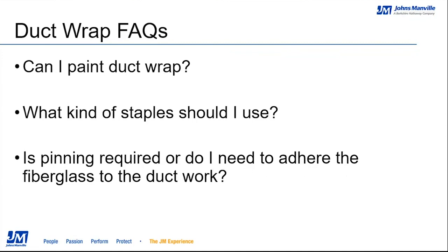using, and therefore we can basically say it's going to void our warranty if you paint the duct wrap, because we've never tested that composite material in that test environment. So you've got to make sure you check with the fire marshal depending on what you're painting it. Now, we did launch our white PSK product and our black PSK product because the two most commonly asked for colors to paint duct wrap are white and black.